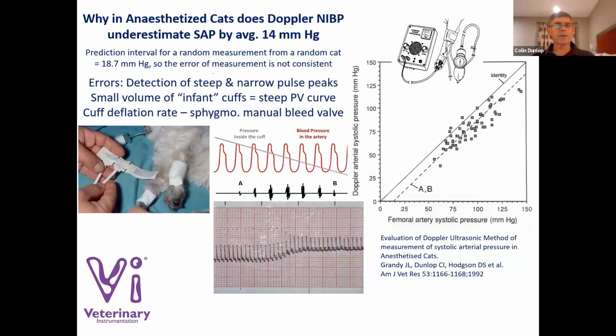If we let down the blood pressure cuff with a Doppler in a cat, what we're relying on is the Doppler, with the rate of deflation in the cuff, picking up the peak systolic point. And the problem in cats and small dogs is that this peak is very narrow and we often can't pick that up. It's not big enough. There's not enough change in sound or pulsation there for us to detect it. So we come further down into the waveform down here and we pick that up.